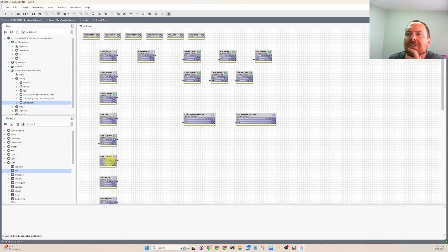Here's our 65 degree set point to enable the chiller. Okay, so my assumption is if we set, let's see, 70 degrees, run the chiller. Did the chiller run? Ooh, I do see chiller points. Hopefully these were false before that. And then a chiller pump.